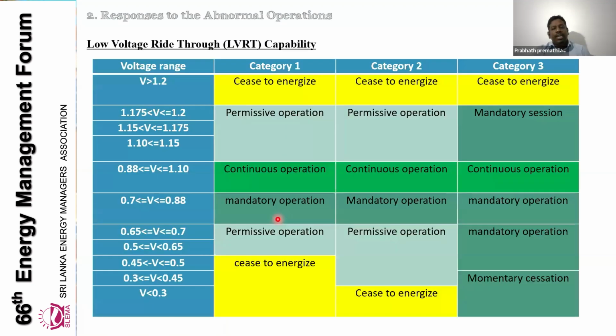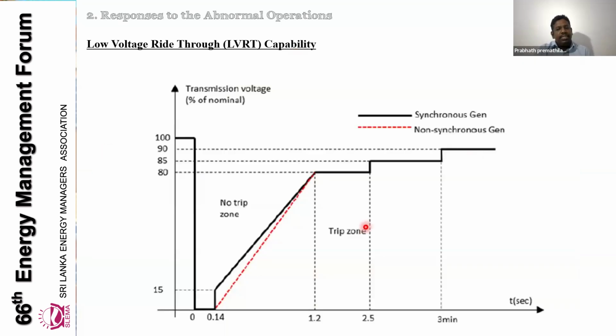Instead of tripping, we can ask the inverter to operate in one of these operation modes. Maybe mandatory operations: it should continue the reactive power support and inject the active power. Or maybe we can ask them to cease to energize. And if the disturbance is over and the voltage is recovered, they can inject whatever power they had before the event. Likewise, we can ask the inverter to support during a disturbance event. This is in the grid connection code, and also in the inverter settings very recently published by the Sri Lanka Electricity Board. This is the low voltage LVRT curve we follow.